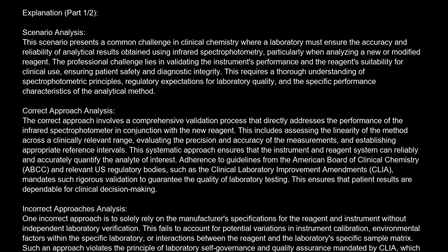The professional challenge lies in validating the instrument's performance and the reagent's suitability for clinical use, ensuring patient safety and diagnostic integrity. This requires a thorough understanding of spectrophotometric principles, regulatory expectations for laboratory quality, and the specific performance characteristics of the analytical method. Correct approach analysis. The correct approach involves a comprehensive validation process that directly addresses the performance of the infrared spectrophotometer in conjunction with the new reagent. This includes assessing the linearity of the method across a clinically relevant range, evaluating the precision and accuracy of the measurements, and establishing appropriate reference intervals.